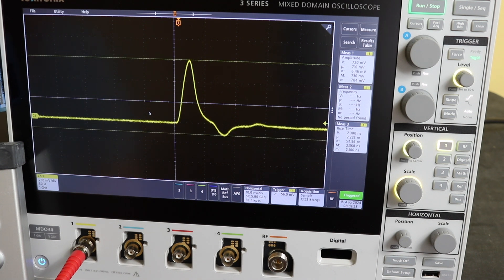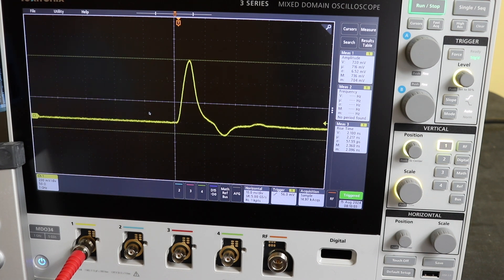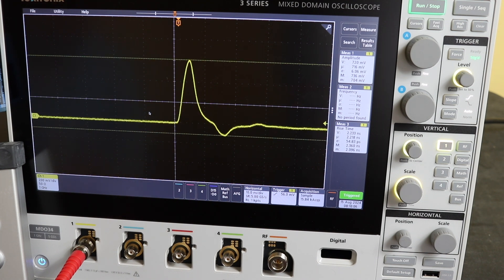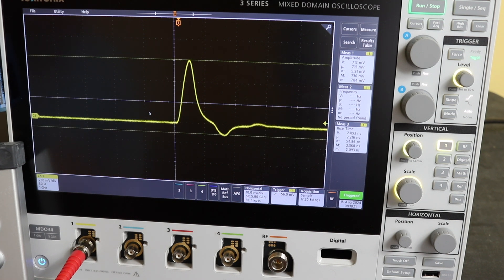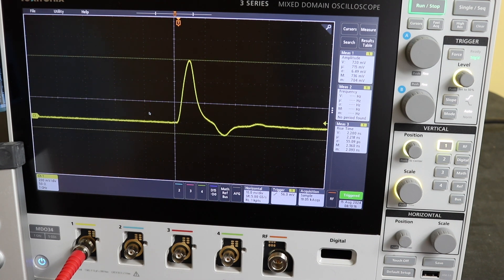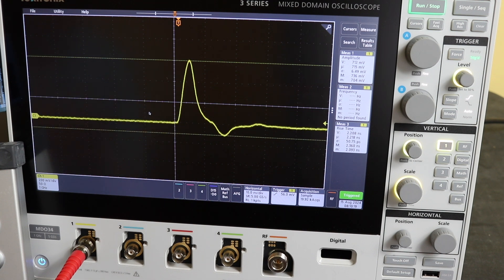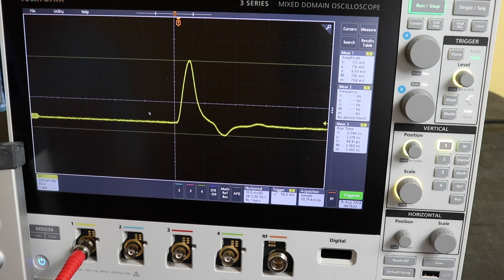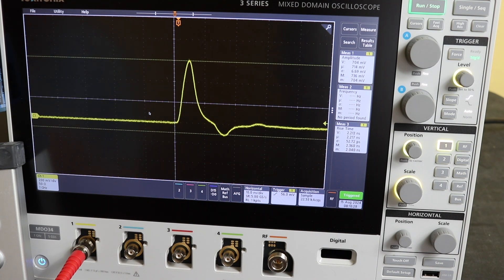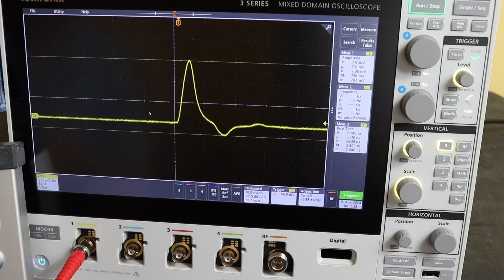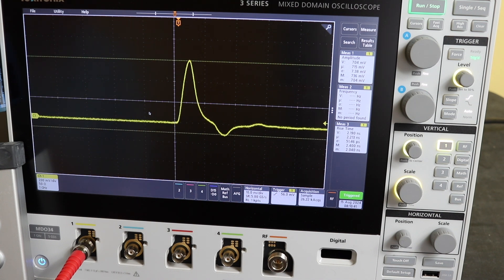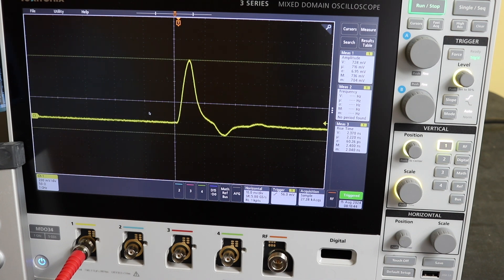So there you have it, that's the little discharge signal there. As I said, I will take a number of measurements of this and record values as a baseline. Then when I come back to recheck the operation of this calibrator again I can call these back up and compare and trend them over time to see that the unit isn't failing. Obviously all I can do is monitor this. If the unit does produce an error then I will have to send it back to the manufacturer for repair or calibration or probably even buy a new one depending on what the relevant costs are. But that'll be it for this video. As I said it's probably got limited interest to people but I thought I'd put it out there anyway. Thanks very much for watching, hope you found it useful and I'll see you again in the next one.